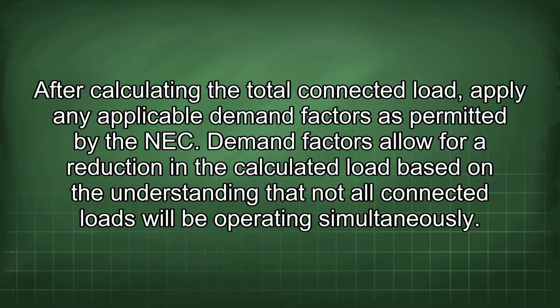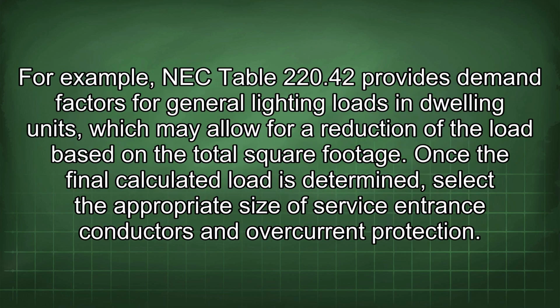After calculating the total connected load, apply any applicable demand factors as permitted by the NEC. Demand factors allow for a reduction in the calculated load based on the understanding that not all connected loads will be operating simultaneously. For example, NEC Table 220.42 provides demand factors for general lighting loads in dwelling units, which may allow for a reduction of the load based on the total square footage.